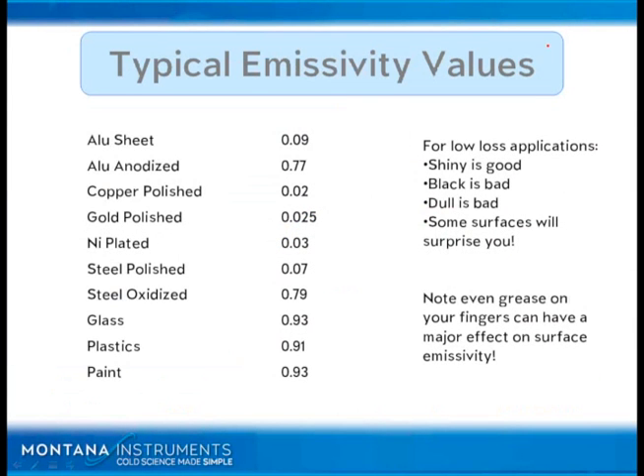Here's just really quickly we've got some emissivity values. Notice that glass here is 0.93. When I'm calculating running numbers, I just use 1 to be conservative. Samples are typically an emissivity somewhere in this range, one or just slightly below.